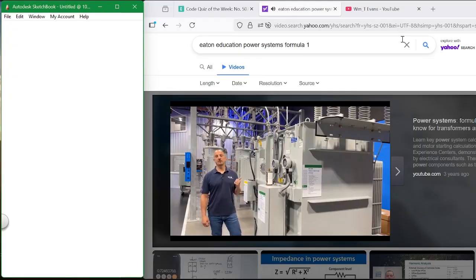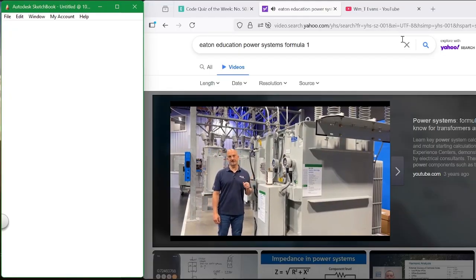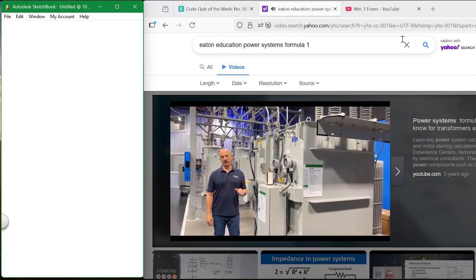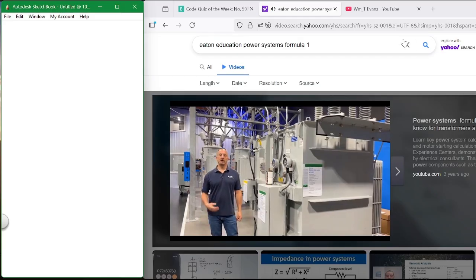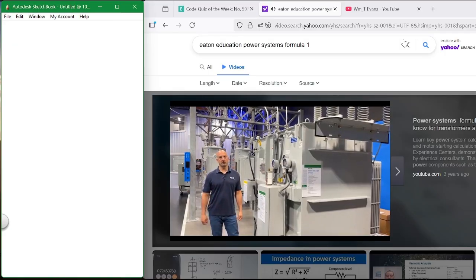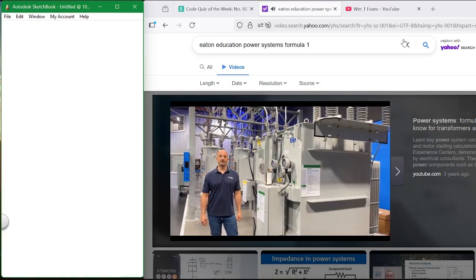So this transformer is 5,000 kVA, but it also has a slash rating of 6250. And that's because we have fans and radiators on the back to cool it down so the oil can move through those radiators and we get more kVA out of the transformer. That's going to come into our calculations for full load amps and also our fault current a little bit differently, so we have to think about that. This one has 34.5 kV in, 13.8 kV out.